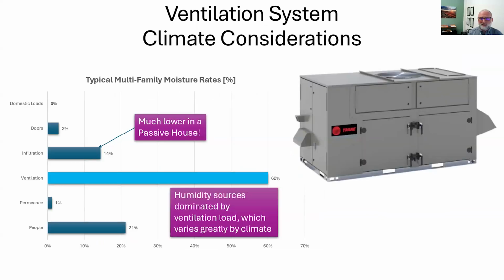Another important consideration is humidity control. A lot's been said about the problems associated with humidity buildup in tight, well-insulated buildings. This is because insulation and shading reduce the cooling load in these buildings, so the air conditioners run less often, which allows latent loads to go untreated and humidity can build up in the space. It's important to recognize that for most building types and most climates, the majority of the humidity load comes in with the ventilation air and from infiltration.